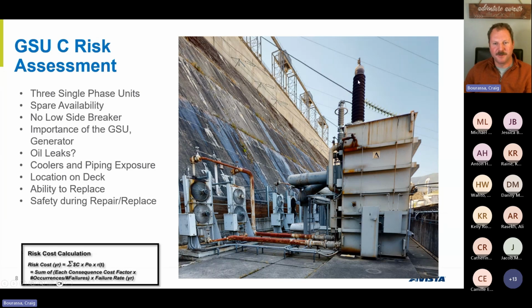So let's walk through this one. We have three single phase transformers and we don't have a spare for it. So if one of these were to have a fault, we'd have an opportunity cost associated with an outage. If this were to fail, it might take 18 months to replace it, so this 100 megawatt unit at the plant would likely be down until we could get a replacement, maybe a year and a half. That's a lot of risk, so you quantify that risk and the probability that one of these were to fail.